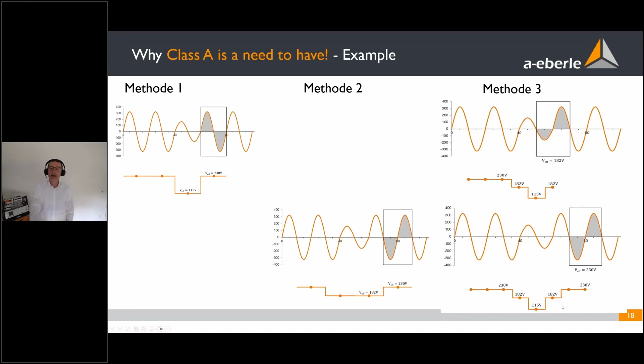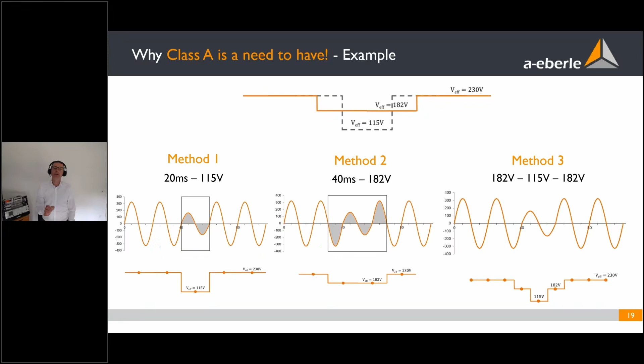The point is, as you could see, different methods have different results. In method 1, we have the result that this dip was 20 milliseconds, 115 volts. With method 2, we have 40 milliseconds, 182 volts. With method 3, we have a shift of always 10 milliseconds. We have 182 volts, 115 volts, and then afterwards 182 volts. And the longest point is here 10 milliseconds. And the question is, what is valid for fault ride through? What is valid for fault ride through can only be a measurement result which is explained, which is defined.